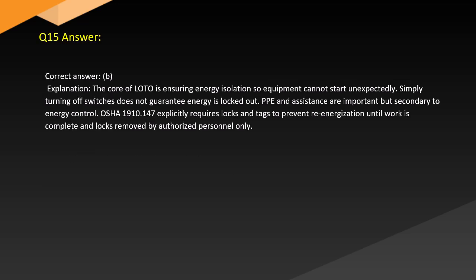Answer. Correct answer: B. Explanation. The core of LOTO is ensuring energy isolation, so equipment cannot start unexpectedly. Simply turning off switches does not guarantee energy is locked out. PPE and assistance are important but secondary to energy control. OSHA 1910.147 explicitly requires locks and tags to prevent re-energization until work is complete and locks are removed by authorized personnel only.